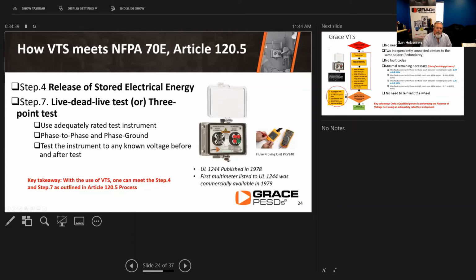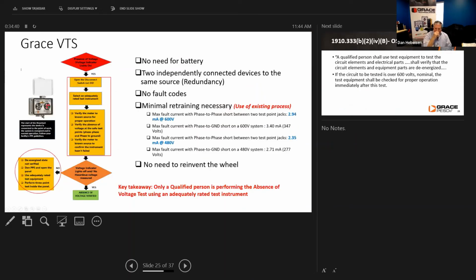These products are becoming very popular because they isolate the individual from the high incident energy and give them the opportunity to do that testing from outside the cabinet. A couple other key factors. There's no need for a battery in this. You actually have 2 independent devices connected to the same source, redundancy, that are telling you in a visual format that there is no energy there, as well as the safe test point, which is giving you the opportunity to do your metered and measured test.